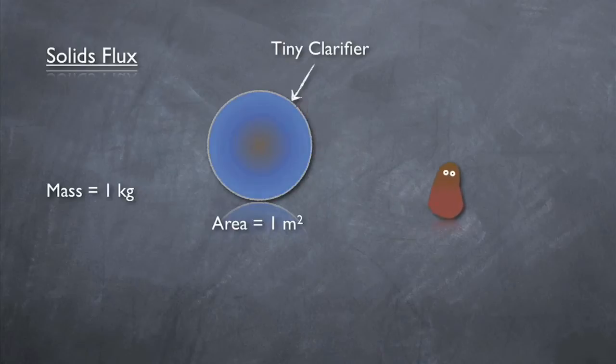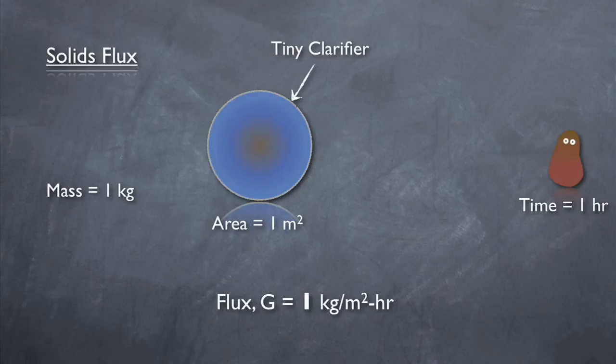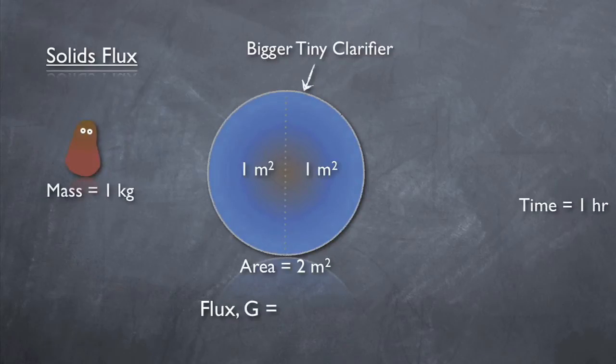Imagine a tiny clarifier with a surface area of only one square meter. The flux in this case would be equal to the total mass of solids passing through the clarifier in one hour. So if one kilogram of mass were to pass through in one hour, the flux would be one kilogram per meter squared hour. Now if the surface area of the tiny clarifier was doubled, but the same mass of solids passed through in the same amount of time, the solids flux would be half.